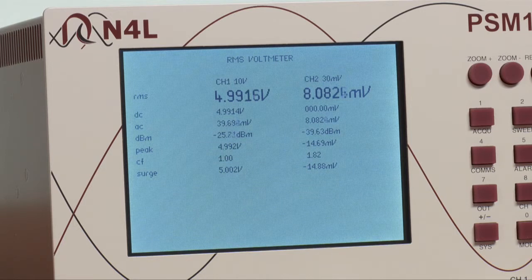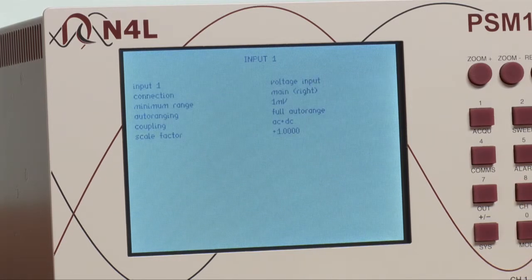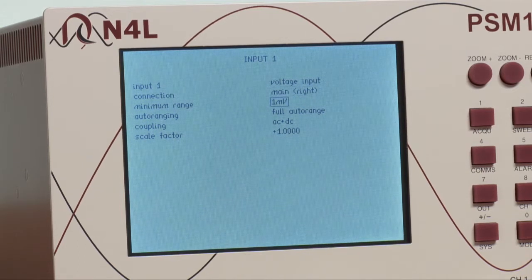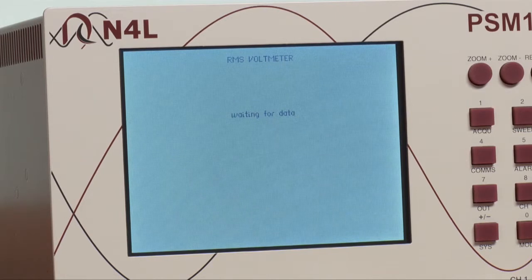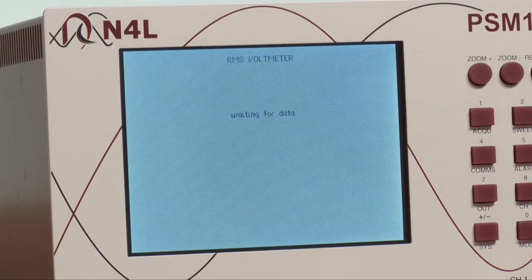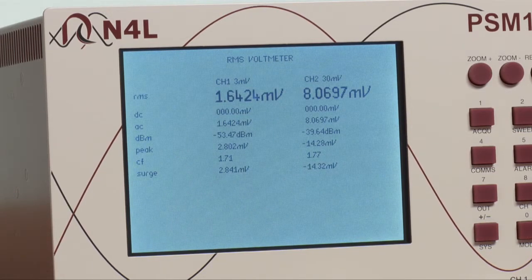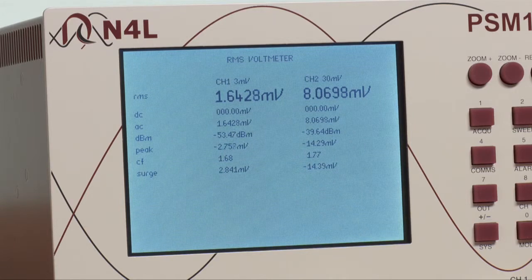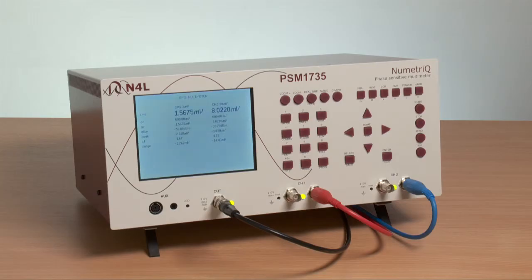We are going to set the AC coupling mode for channel 1 by going into the channel 1 menu, because for frequency response analysis we are interested in only the AC component. Now you see 1.6 millivolts on channel 1 and 8 millivolts on channel 2. Channel 1 is the input and channel 2 is the return. So there is gain.